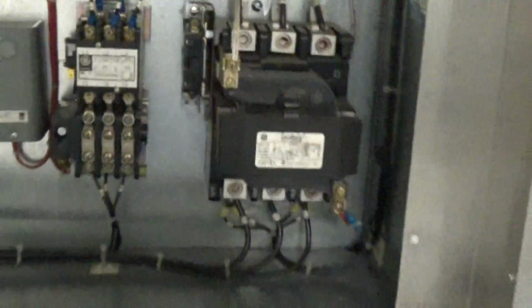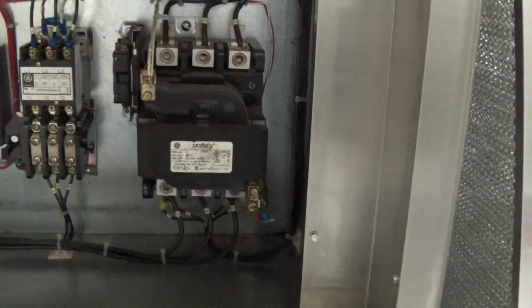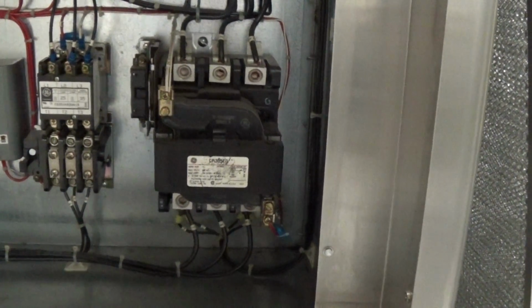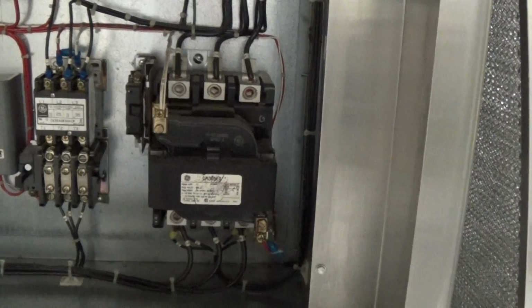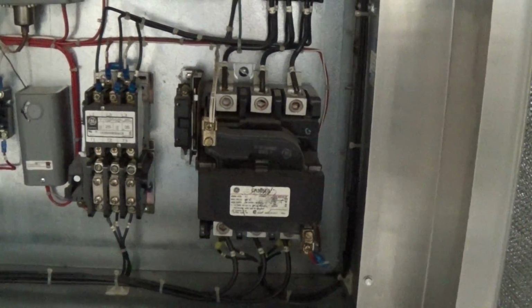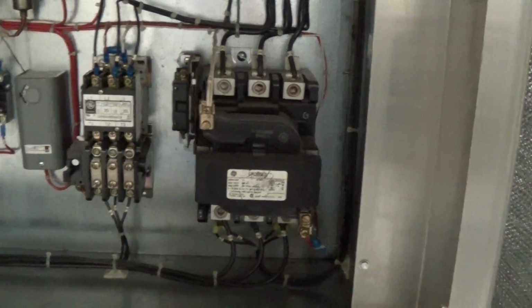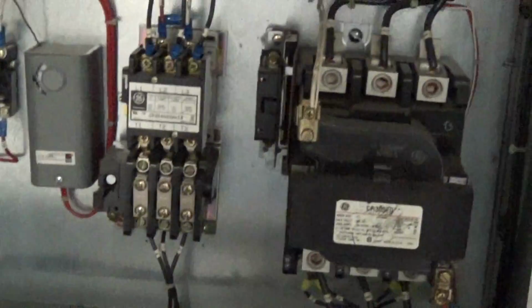And lastly, the inside of the unit here. This is our main contactor. It is 3-phase power. Rotation is critical. So when you first power this unit up, you have to have the cabinet off and somebody inside there looking at the rotation of the pump. That's walked through in the manual.